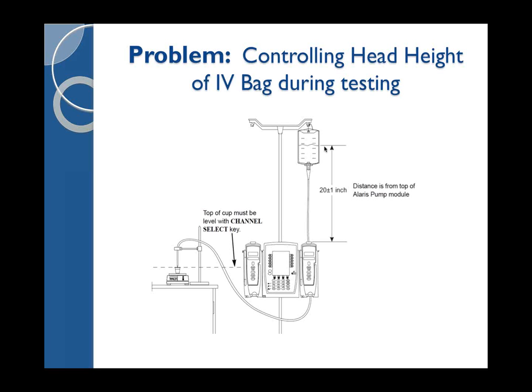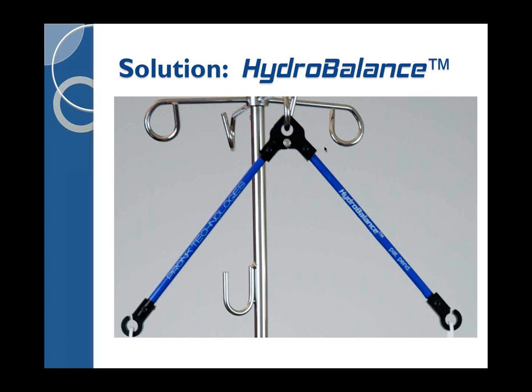So we looked at that, and we're seeing the results of that, and we showed it in the previous slide, that you can see up to a 1% reduction as the fluid height goes from 20 inches down to 12 inches as the bag gets emptier. We could see that influence of that fluid height, and we're trying to find a way to solve it both for ourselves and for the market. And what we discovered was that you could deal with that fluid height changing over the course of a day's time, and we designed what we're calling the HydroBalance to maintain that fluid height inside the bag over 50 or 60 pump tests.